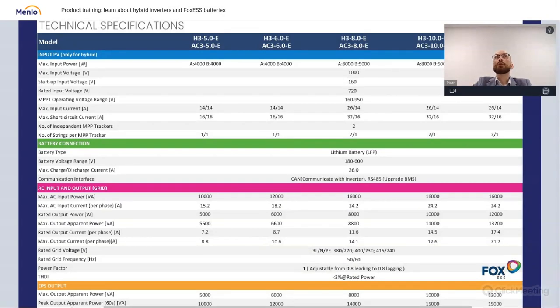Maximum input voltage is 1000 volts. Please remember that this is the maximum voltage for this system to operate. That doesn't mean that you have to build your PV array or your PV string with this 1000 volts in mind. Please keep your strings, your voltage on your tracker, in the optimum for every inverter. And this optimum is about 600 to 650 volts. If you provide 700 volts for this unit, it would be perfect. It would be really a sweet spot, an optimum for this unit to operate.